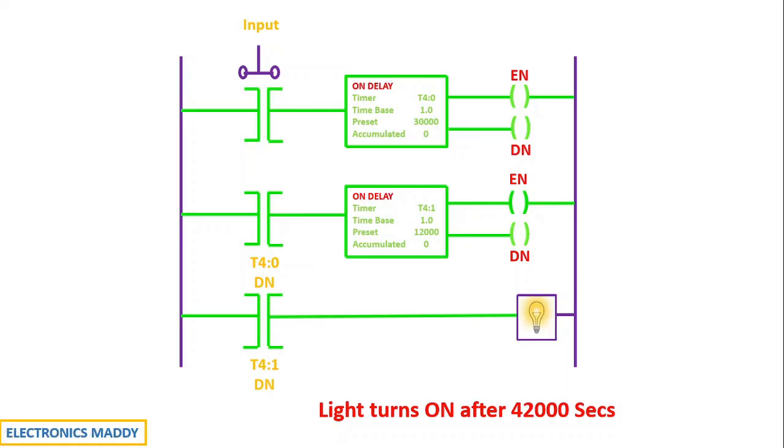But the question is, why do we need cascading? Why can't we use one particular timer to count 42,000 seconds? That might be a common question you might be having now. The answer is pretty simple and straightforward. In certain PLCs, the maximum count value of timers might be 32,767.